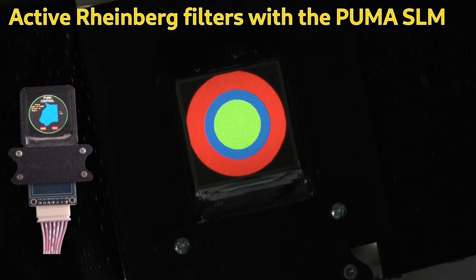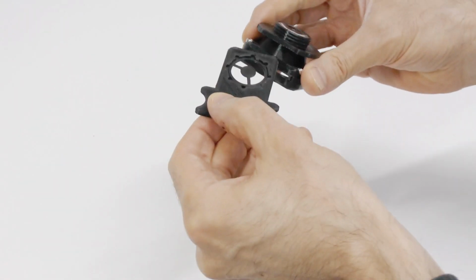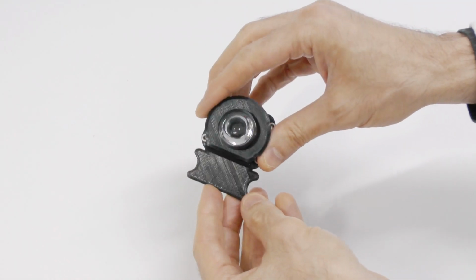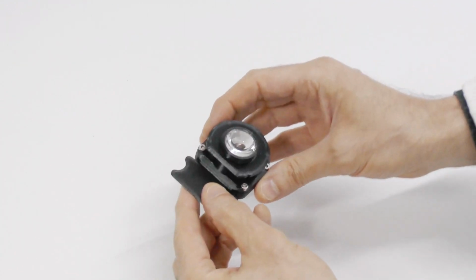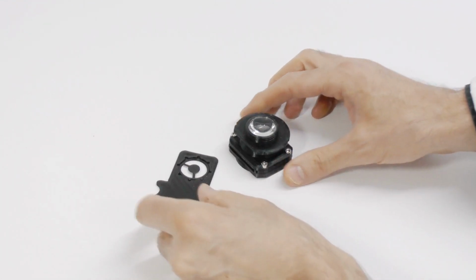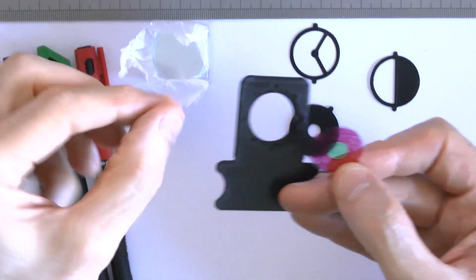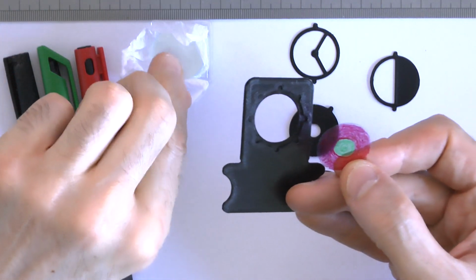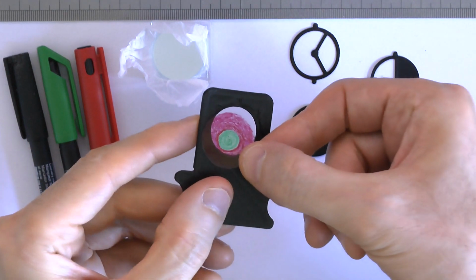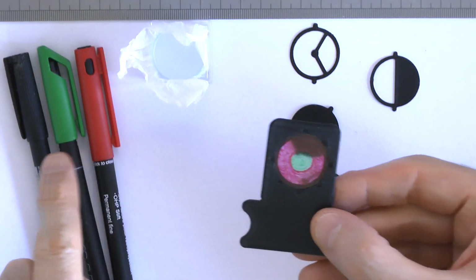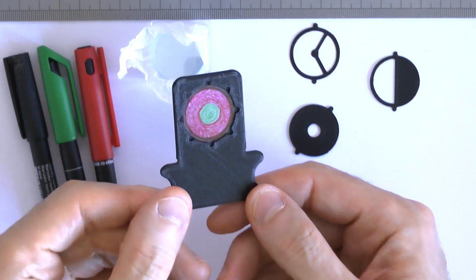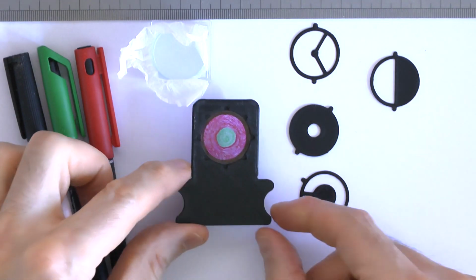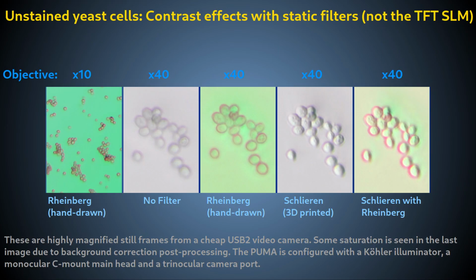You can implement some advanced contrast methods without this SLM, using PUMA's easy-to-access Fourier plane of the condenser with a simple filter system. This filter tray can take a standard 25mm round glass cover slip on which you can print any arbitrary aperture in black and white or various colors. So, you don't need this TFT SLM for doing things like Rheinberg filters, oblique illumination, Schlieren phase contrast, dark ground illumination, and other static custom apertures.